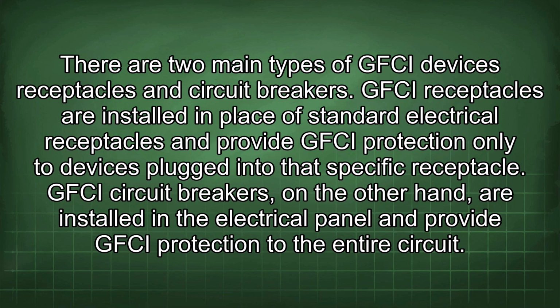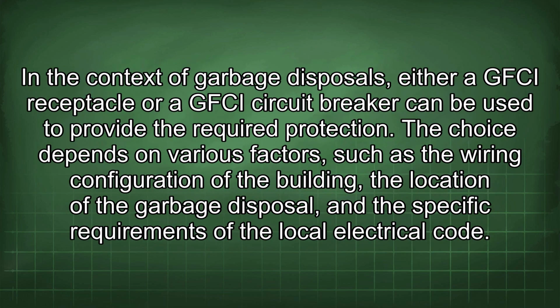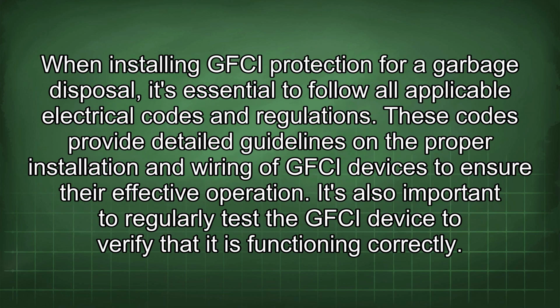the entire circuit. In the context of garbage disposals, either a GFCI receptacle or a GFCI circuit breaker can be used to provide the required protection. The choice depends on various factors, such as the wiring configuration of the building, the location of the garbage disposal, and the specific requirements of the local electrical code. When installing GFCI protection for a garbage disposal, it's essential to follow all applicable electrical codes and regulations. These codes provide detailed guidelines on the proper installation and wiring of GFCI devices to ensure their effective operation.